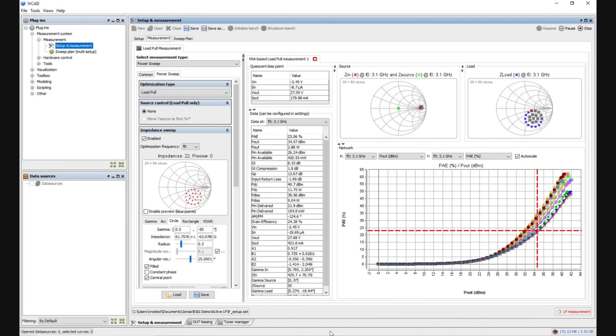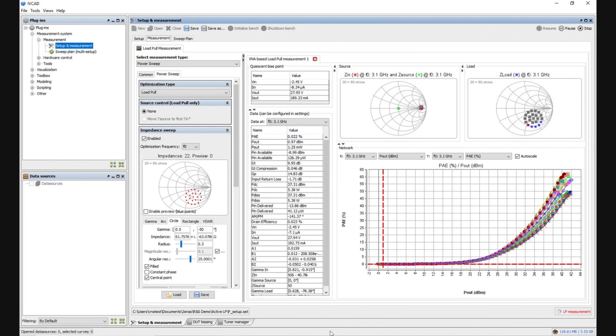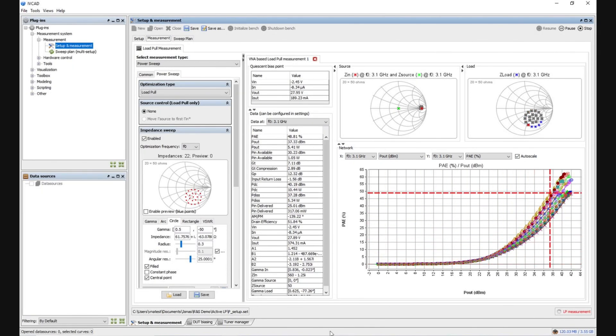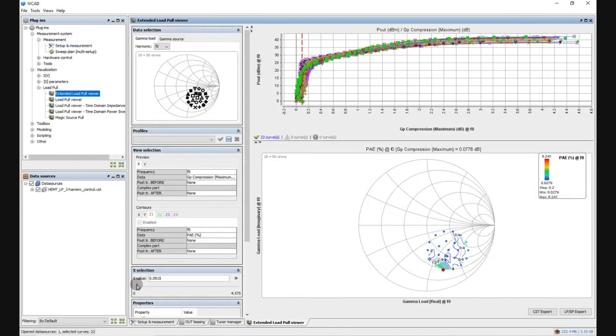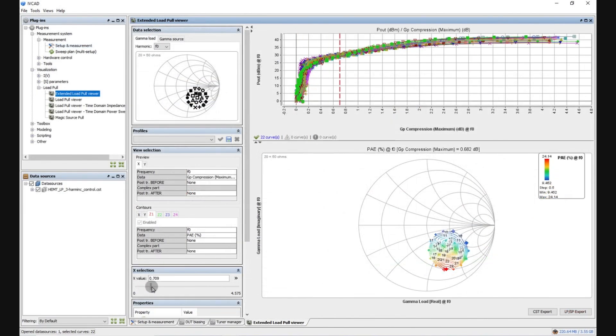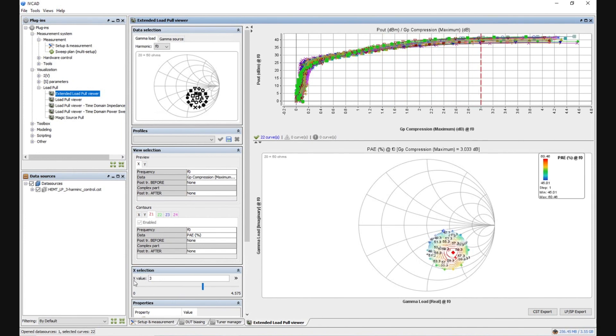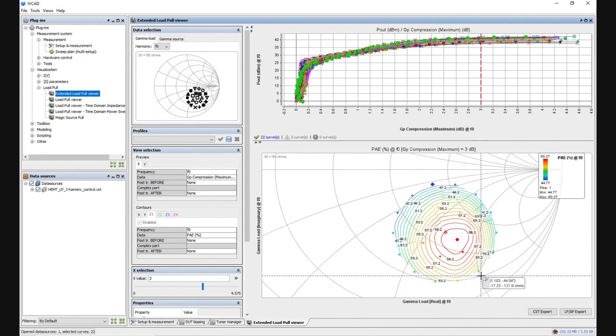Moreover, the DUT input and load impedances are measured for each power level and plotted on the two Smith charts at the top of the measurement window. After the measurement is finished, we can analyze the measurement data using IVCAD's advanced data visualization tools and plot the device parameter contours against the desired gain compression value.